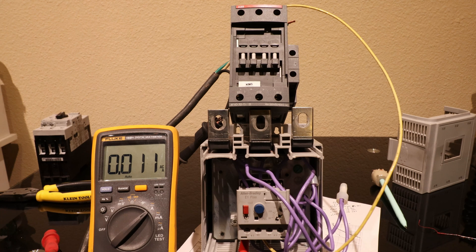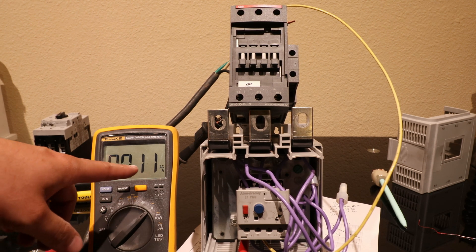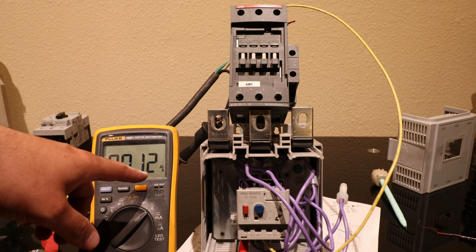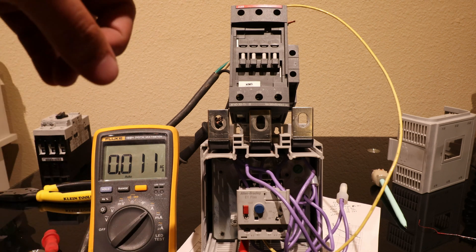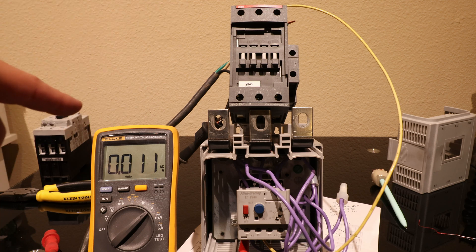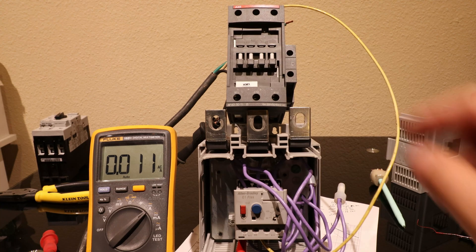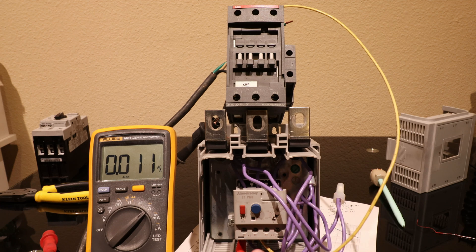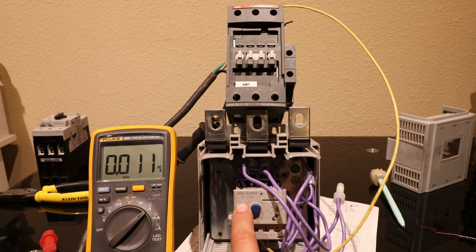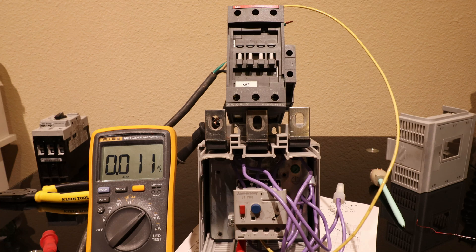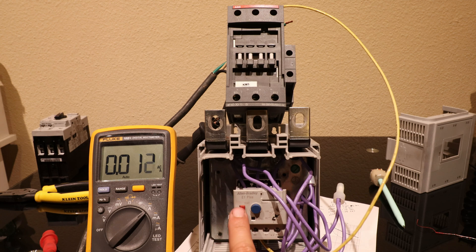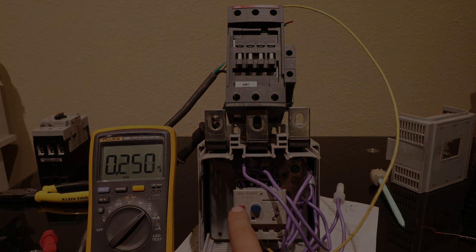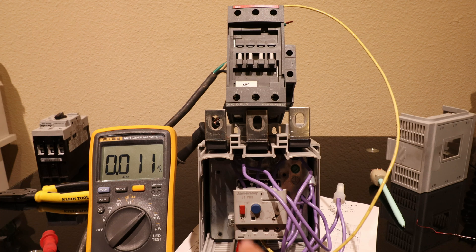Wow that's barely anything. That is 0.011 amps alternating current, so 11 milliamps. That can't be right. We're going to ohm out this solenoid in a second and see if that corresponds to the amperage that it's pulling with 120. So right now contactor pulled in. Whenever you want to test, you can test. We'll open these contacts and cut off power to the contactor.